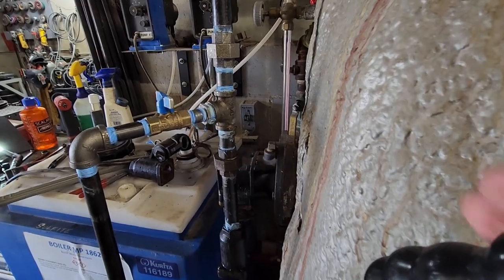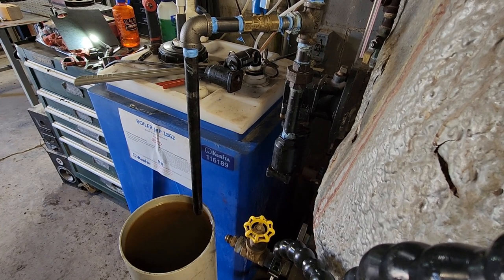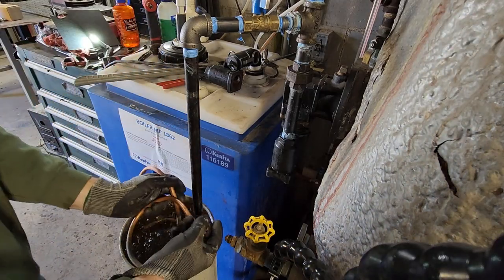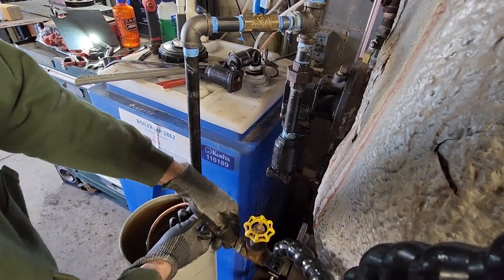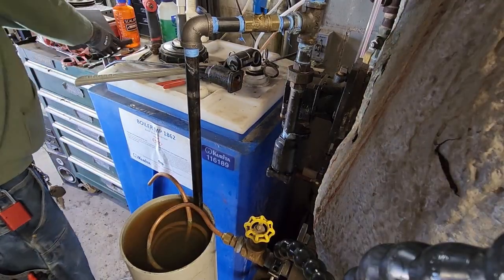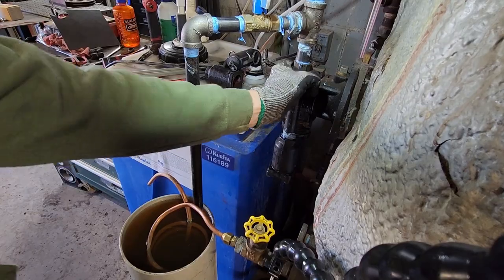Okay, got a phone call from the boiler people. We've had the boiler off long enough that the pressure came down to a level where it'll send an alarm to our monitoring company. I just didn't think this job would take that long, but parts stores running stuff. I should have put the boiler on test. But I didn't, so they called me. No big deal there. I'm just gonna get a couple of these fittings back together.